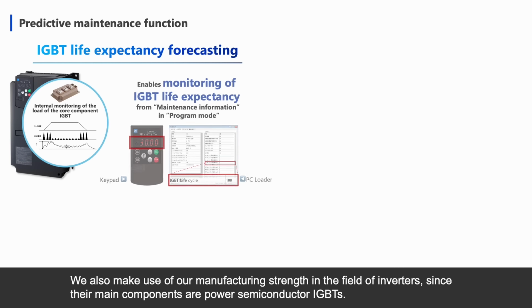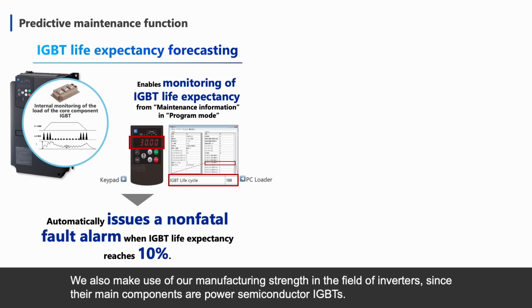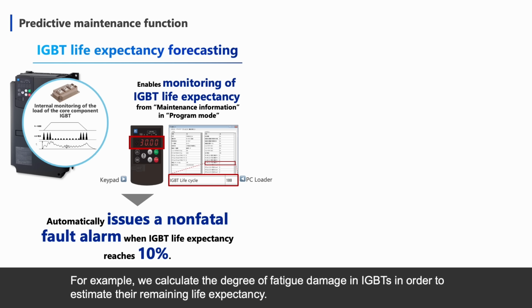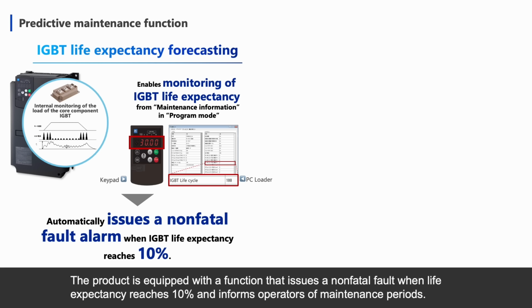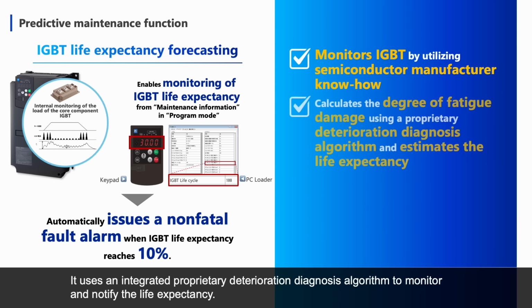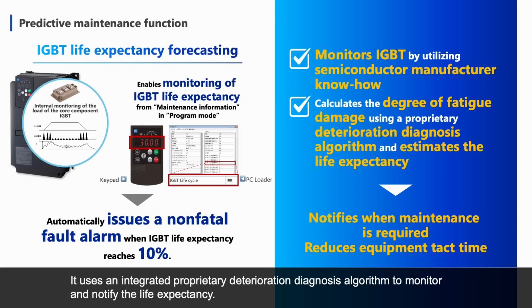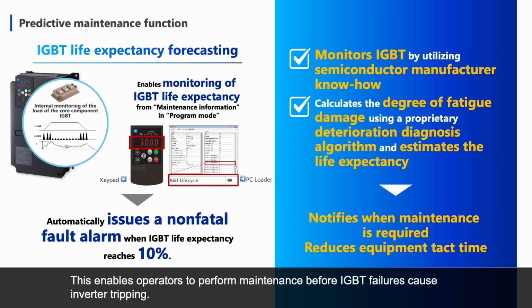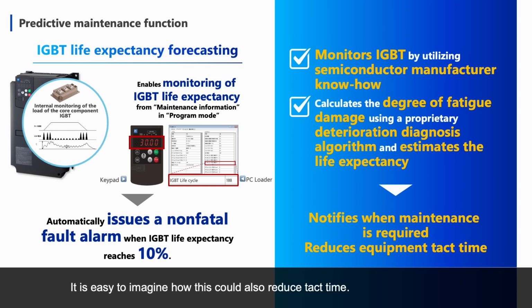We also make use of our manufacturing strength in the field of inverters, since their main components are power semiconductor IGBTs. For example, we calculate the degree of fatigue damage in IGBTs in order to estimate the remaining life expectancy. The product is equipped with a function that issues a non-fatal fault when life expectancy reaches 10% and informs operators of maintenance periods. It uses an integrated proprietary deterioration diagnosis algorithm to monitor and notify the life expectancy. This enables operators to perform maintenance before IGBT failures cause inverter tripping. It is easy to imagine how this could also reduce takt time.